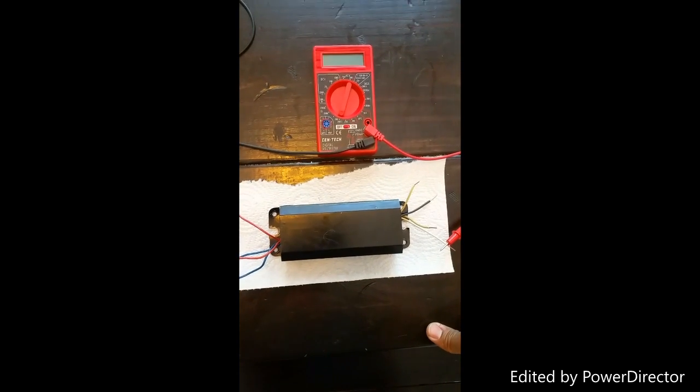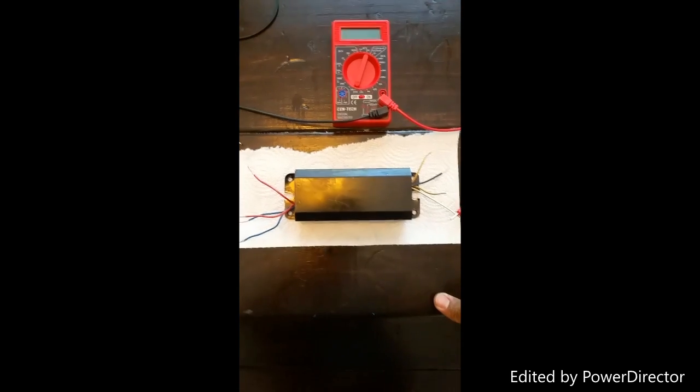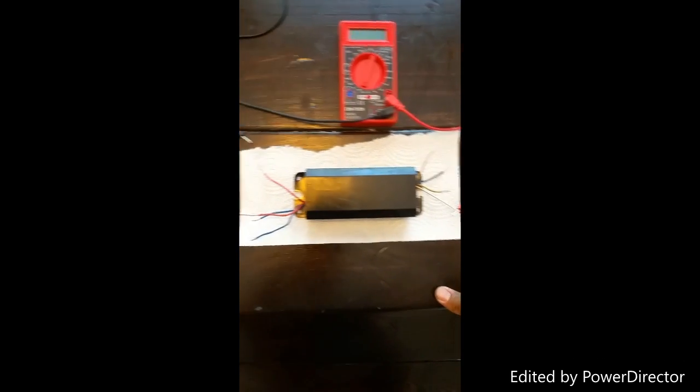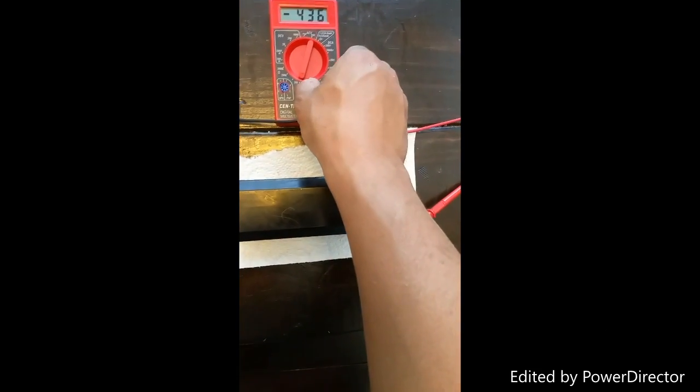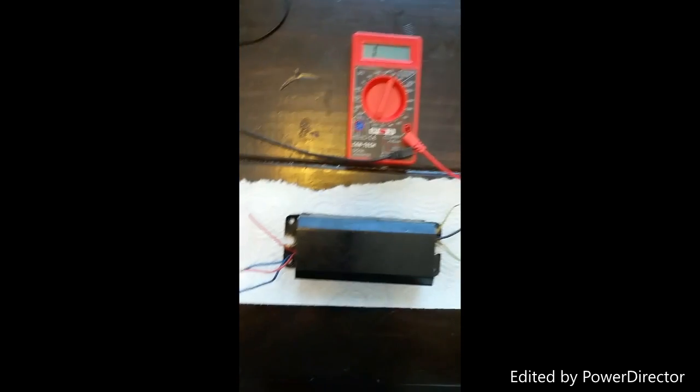I'm going to do a quick video on how to test the ballast in a fluorescent light to see if it's your ballast or some other issue. You want to take your multimeter and set it to ohms, set it about the 1000-2000 range. Mine has a 2000 so I'll just set it there.